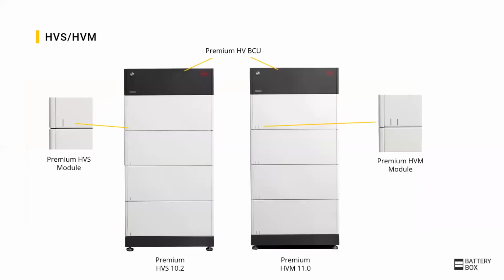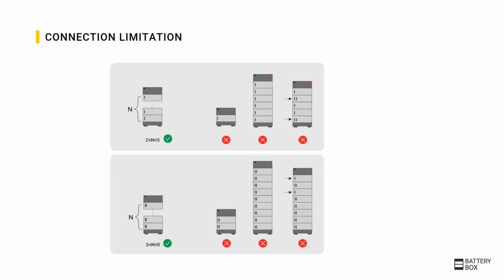When setting up the tower, it is important not to mix HVS and HVM modules. The different modules can be easily differentiated by the lines in the front of the modules. 1 line for HVS modules and 2 lines for HVM modules. The BCU is the same for both versions. Here is shown what is allowed or not possible for one tower configuration. Important here is a correct module quantity and to not mix HVS and HVM modules.